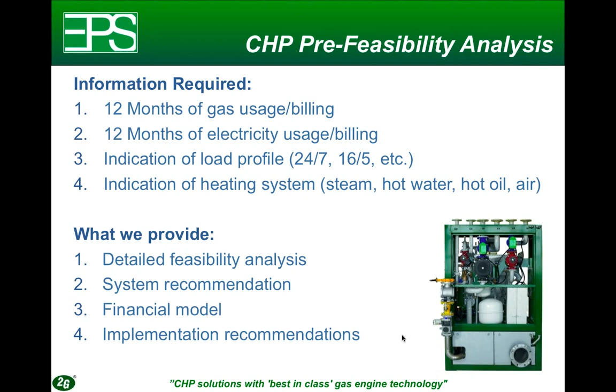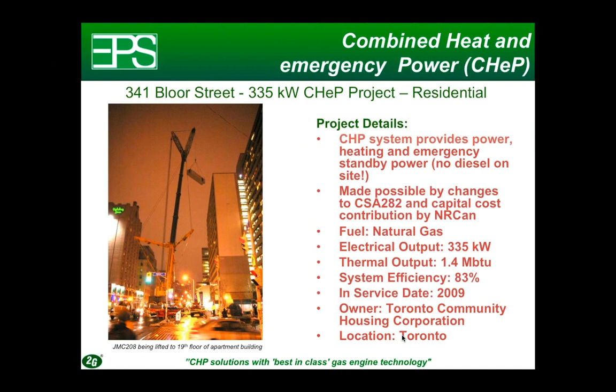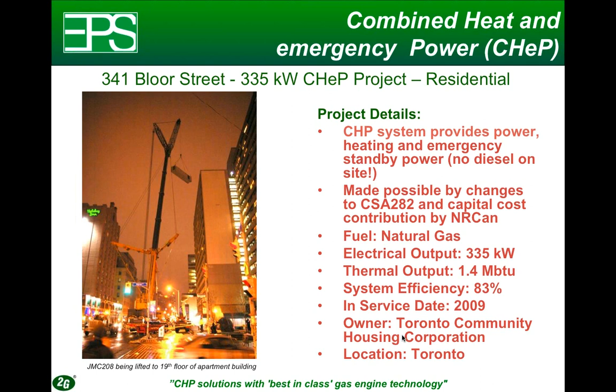Let's look at some project examples from around Ontario and elsewhere. You've heard me talk about combined heat and emergency power — this is a good example. This unit was installed on Bloor Street, right downtown Toronto. The picture shows a crane lifting a containerized unit to the top of a 19-story building, which provides power and heat to this apartment building. It's owned by Toronto Community Housing, and by installing the cogeneration system they no longer require a diesel engine on site; the system provides power, heating, and emergency power to the building.